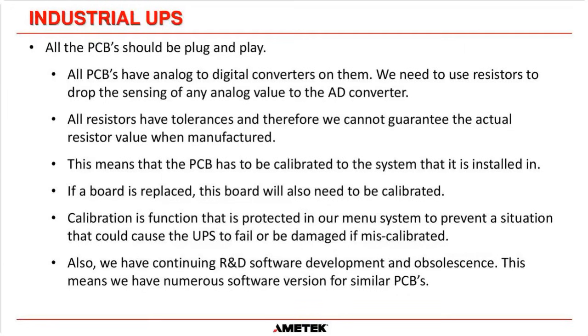Those resistors have tolerances, and therefore we cannot guarantee the actual resistor value when manufactured. That means the PCB has to be calibrated to the system that it is installed in. That's the only way you can calibrate an analog to digital converter: put it in the system, measure the voltages, and then tell the system what those voltages are because of those resistors. And there's also some of the solid state devices, whether it's a processor or an op amp, they have tolerances as well.